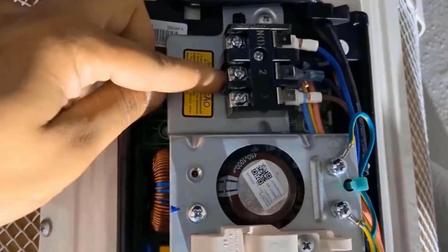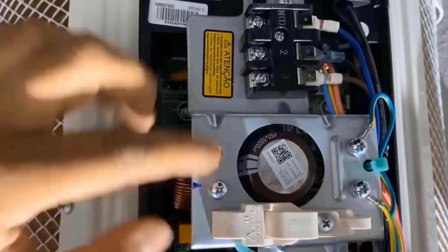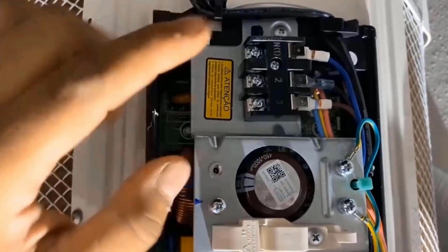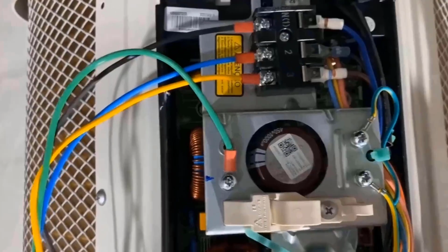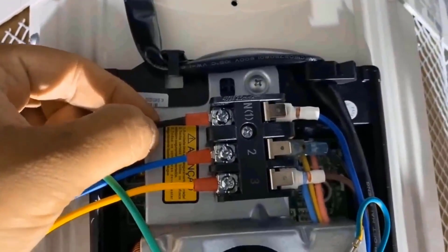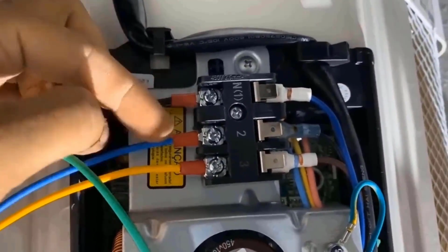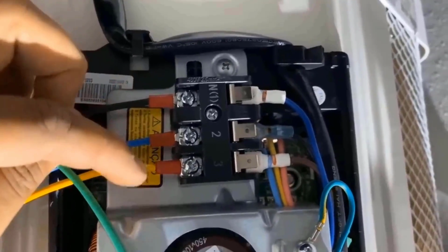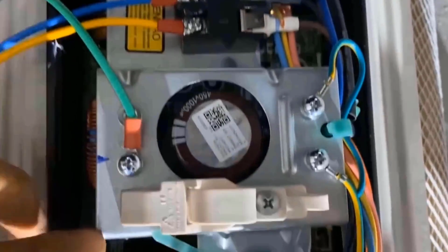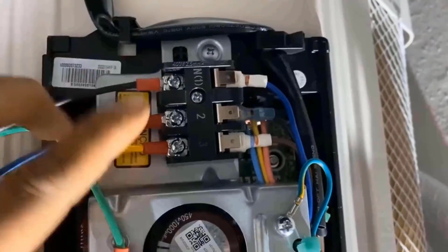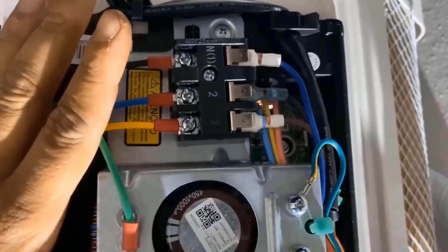In the case of a recent installation, this rarely happens. Generally, what happens in a new installation is that the wires are reversed. The colors of the wires in the evaporator and condenser must match. For example, if the black wire in the evaporator is in position N1, it must also be black in the condenser. Both need to follow the same color scheme to ensure correct communication between the units.